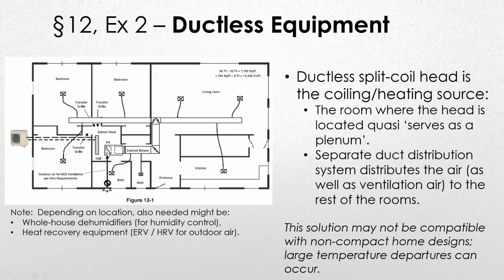intake, because we know the current codes. You could have a 1-ton system that's putting 400 CFM of air in here, but because it's mixing it with the outdoor air and the return air in the space, you could put the 800 or 1000 CFM cabinet blower here and then use conventional air distribution if you so desired.